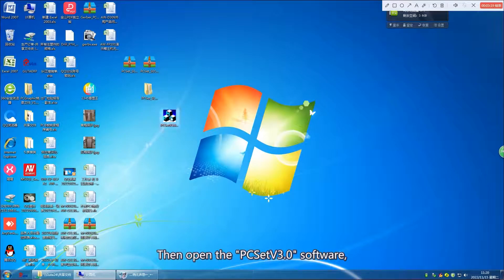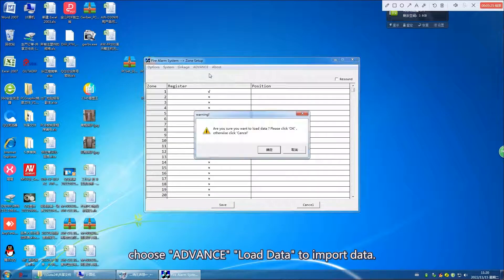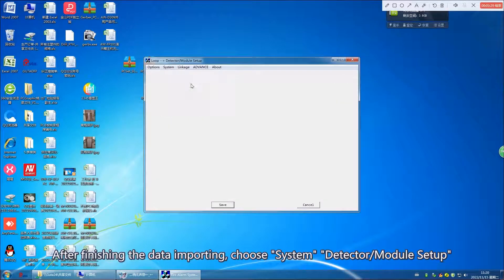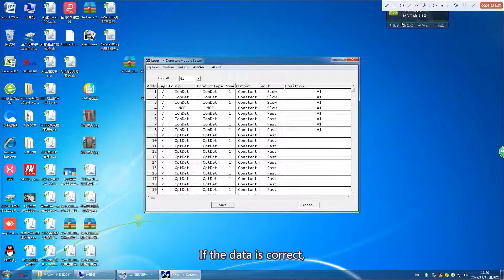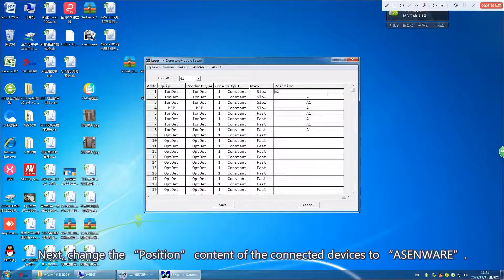Then open the PCSetV3.0 software. Choose Advanced Load Data to import data. After finishing the data importing, choose System Detector / Module Setup to check whether the registered devices are correct. If the data is correct, it proves that the USB is compatible with the panel and the software.